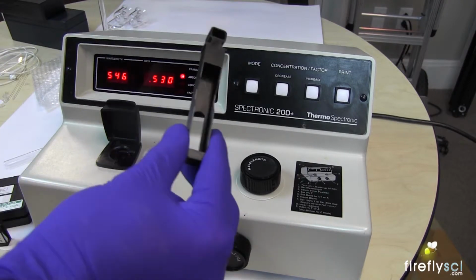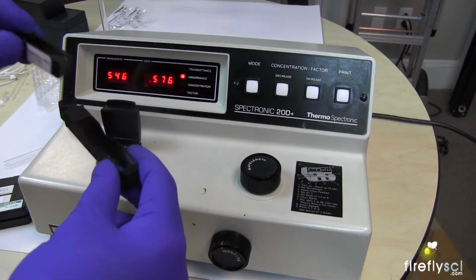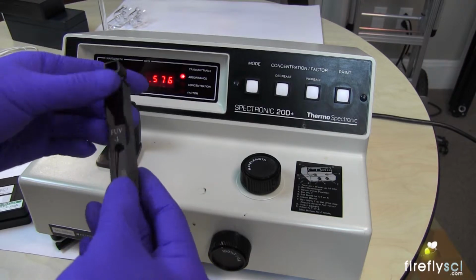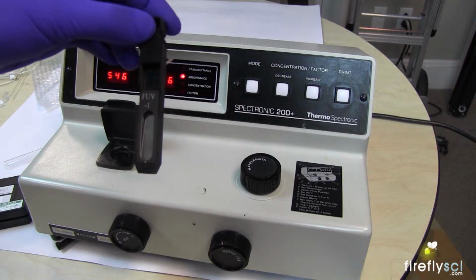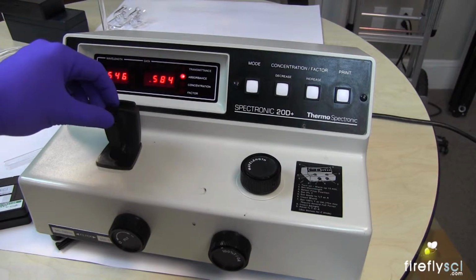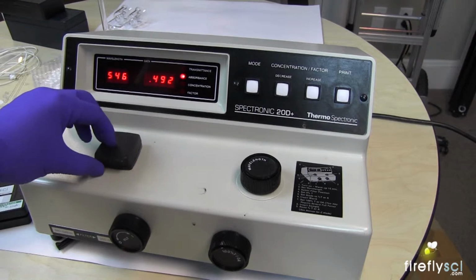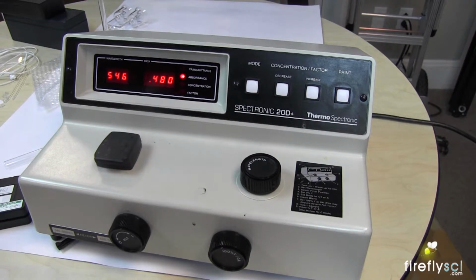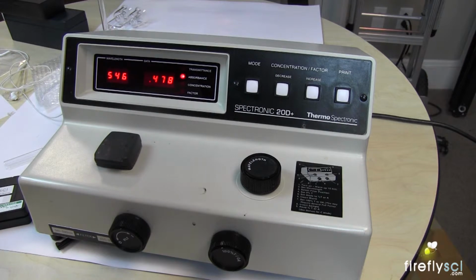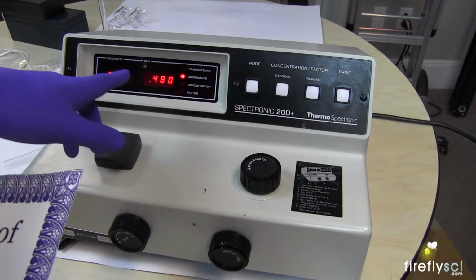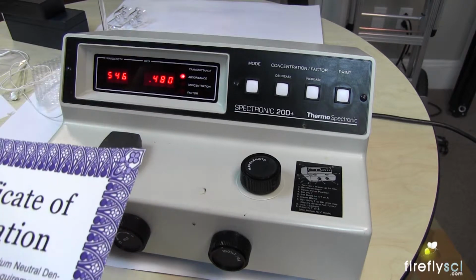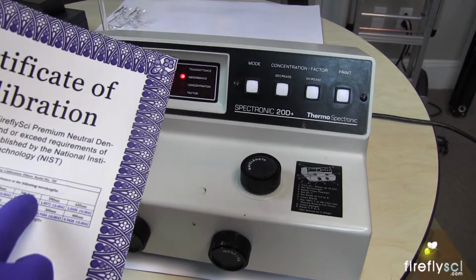Our calibration standard is going to go in this holder now. We can take it back out because you can see how deep this will go into this machine. And send it on down to the bottom. Okay, so let's check out this number. This is an FUV1 filter, so we're looking for a number of like 0.9 to 1, and this is nowhere even close. We're reading 0.480. But let's take a look at the cert anyway.